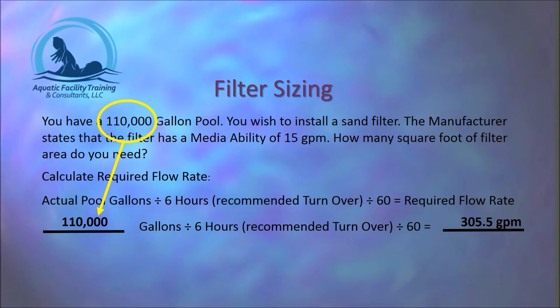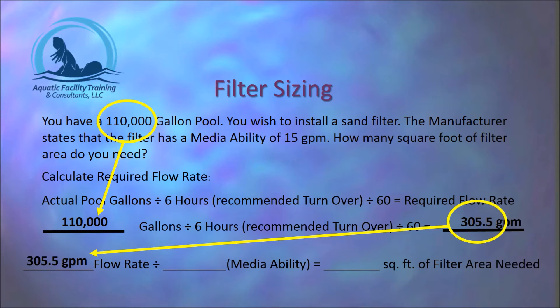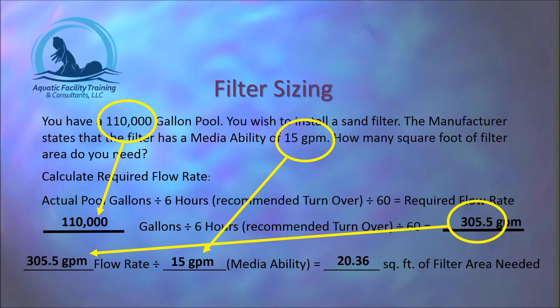We require a flow rate of 305.5 gallons per minute to achieve a 6-hour turnover on a 110,000-gallon pool. Next, we take that 305.5 gallons per minute and divide it by the 15 gallons per minute the manufacturer states this sand filter can handle. 305.5 divided by 15 equals 20.36 square feet of filter area. We require 20.36 square feet of filter area to handle the 305.5 gallon per minute flow rate for a 6-hour turnover.